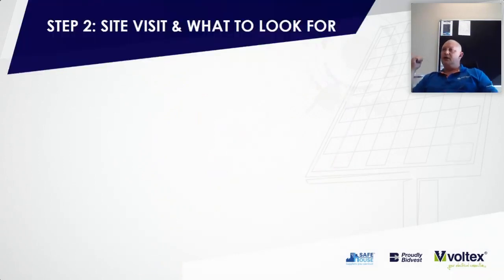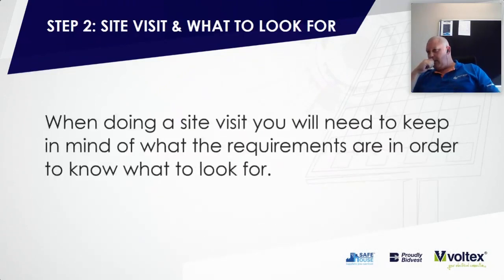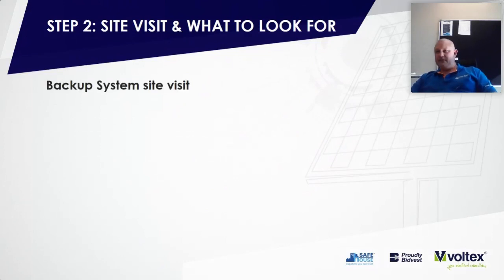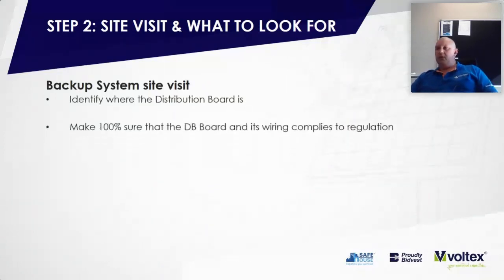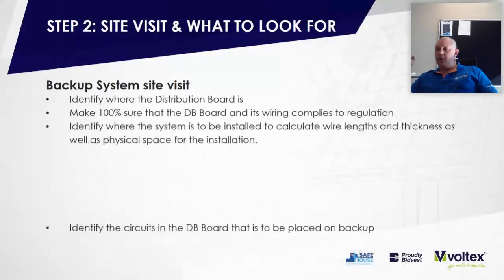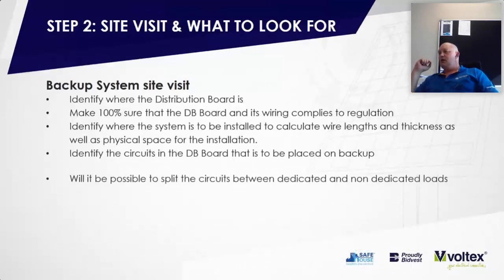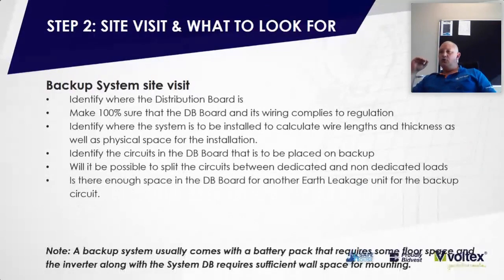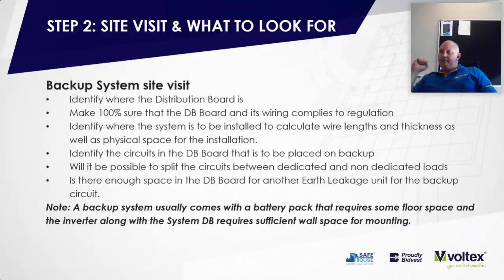Okay, step 2, site visits and what to look for. When doing a site visit, you will need to keep in mind what the requirements are in order to know what to look for. So, a backup system site visit. Identify where the distribution board is. Make 100% sure that the DB is compliant according to the SANS standards. Identify where the system is to be installed. You need to calculate the cable thicknesses according to the requirements, and also identify where you're going to install the system to accommodate for your consumables.